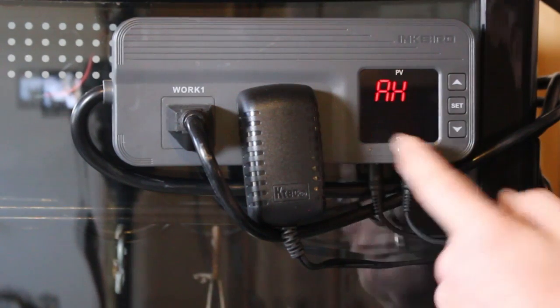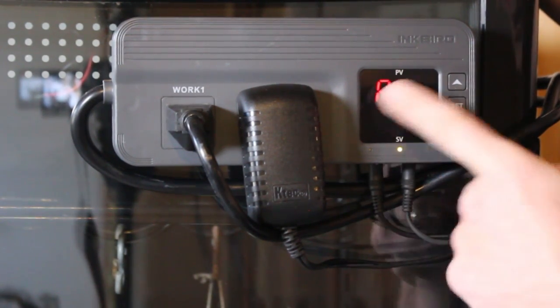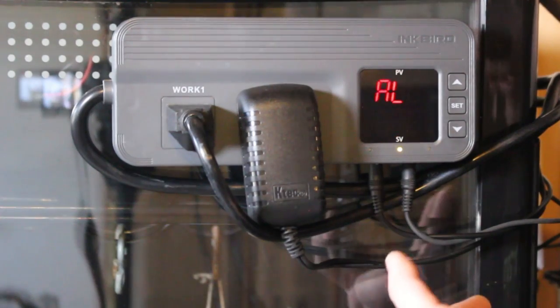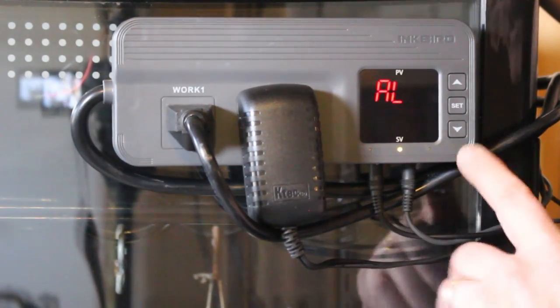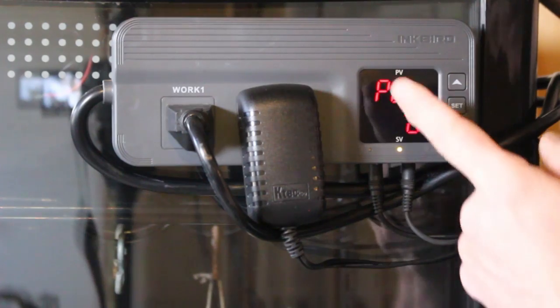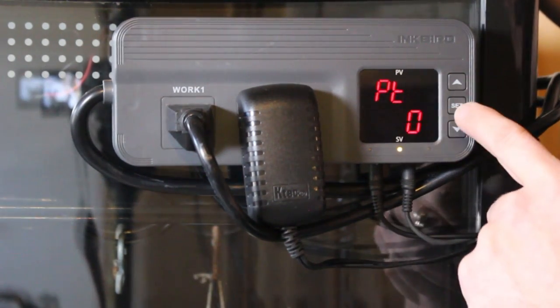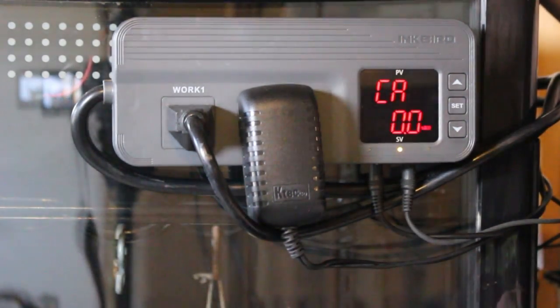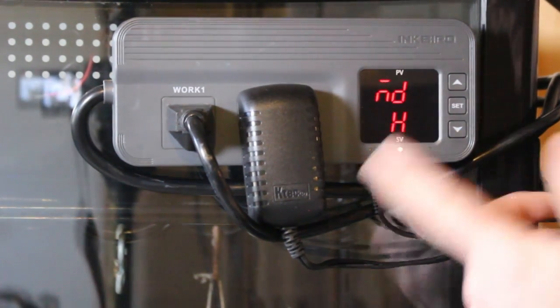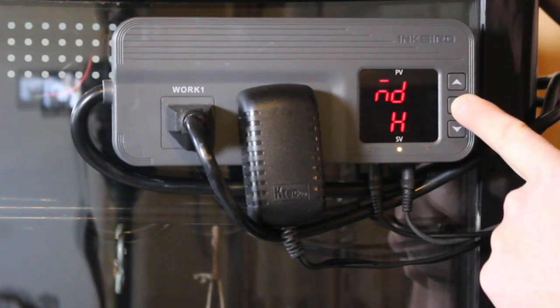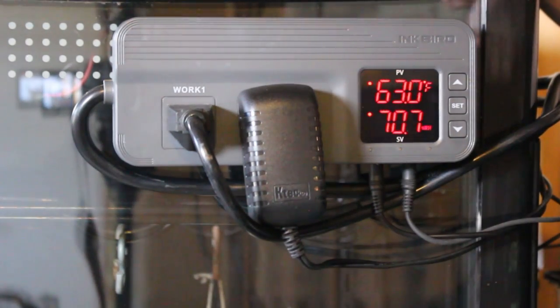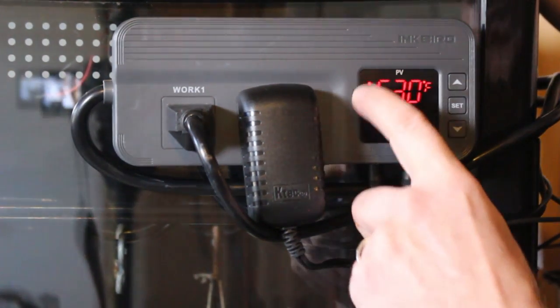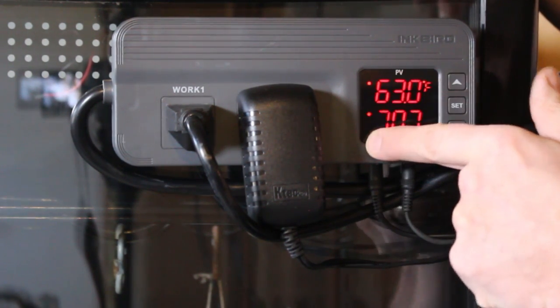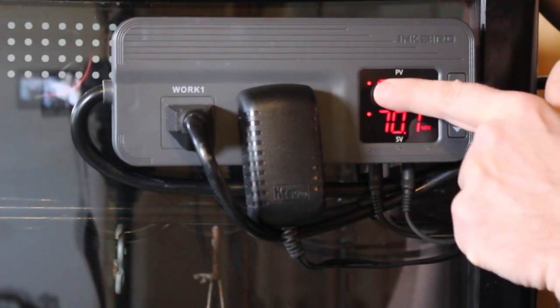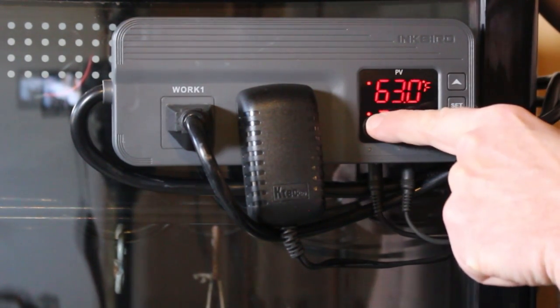Alarm high, 85% relative humidity. I want the alarm to come on. Alarm low, 50% relative humidity. It's getting really dry in there. I don't want to dry my braciole out too quickly. So set an alarm off. Remember our old friend, the compressor timeout. And then my calibration adjustment for humidity. Back to the top. Just hold the button down, and you go back to regular mode. Real neat. There are two little dots here, one's off, one's on. There are two dots here, this one's on, this one's off. So in this line, it's basically saying this is a cooling device, this is a dehumidifying device.